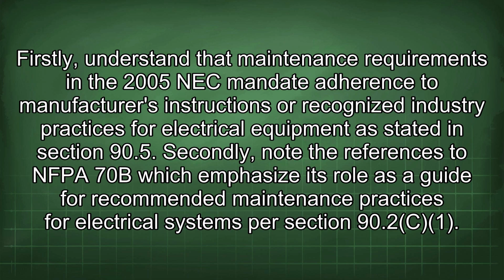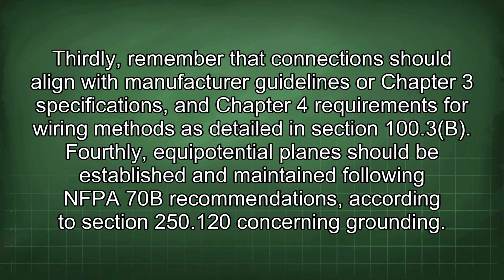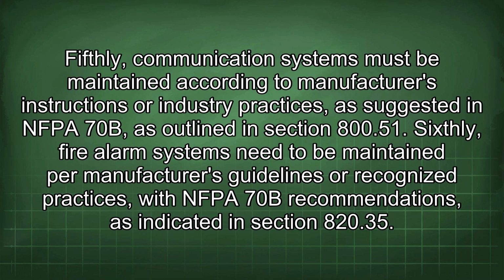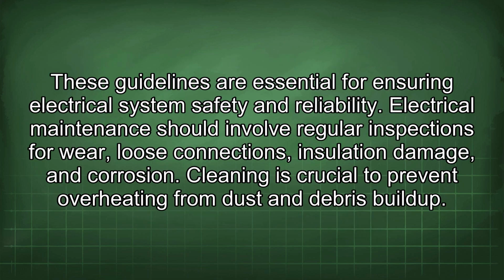Secondly, note the references to NFPA 70B, which emphasize its role as a guide for recommended maintenance practices for electrical systems per Section 90.2. Thirdly, remember that connections should align with manufacturer guidelines or Chapter 3 specifications and Chapter 4 requirements for wiring methods as detailed in Section 100.3b. Fourthly, equipotential planes should be established and maintained following NFPA 70B recommendations according to Section 250.120 concerning grounding. Fifthly, communication systems must be maintained according to manufacturer's instructions or industry practices, as suggested in NFPA 70B, as outlined in Section 800.51. Sixthly, fire alarm systems need to be maintained per manufacturer's guidelines or recognized practices, with NFPA 70B recommendations, as indicated in Section 820.35. These guidelines are essential for ensuring electrical system safety and reliability.